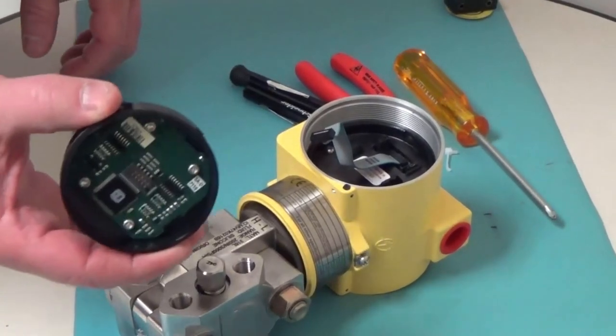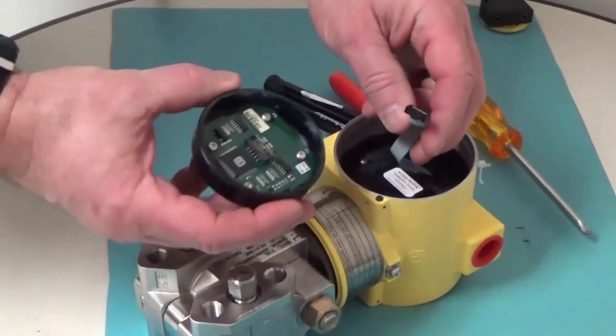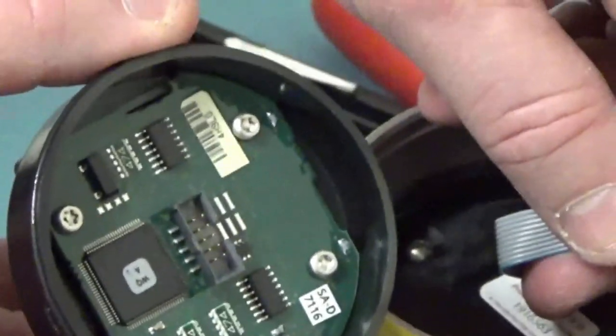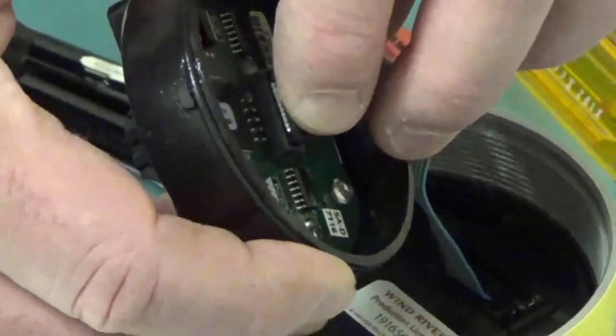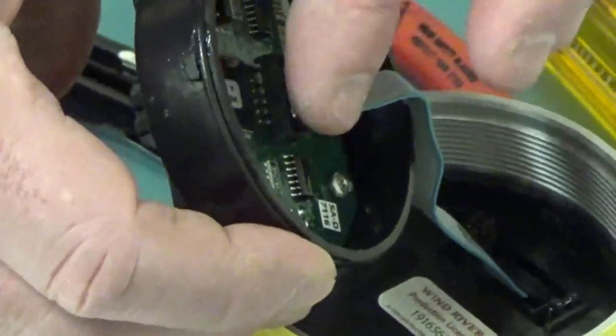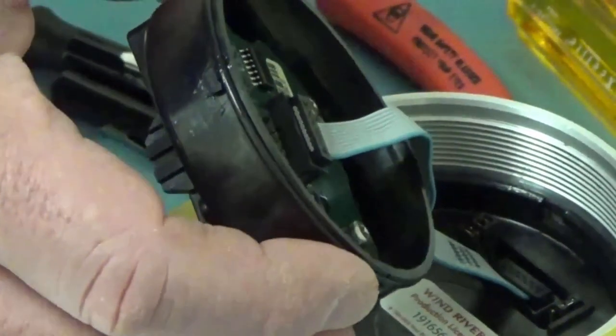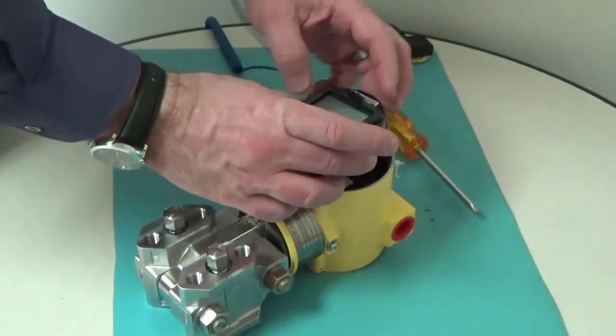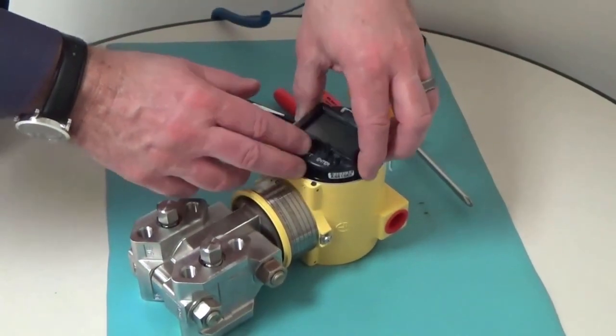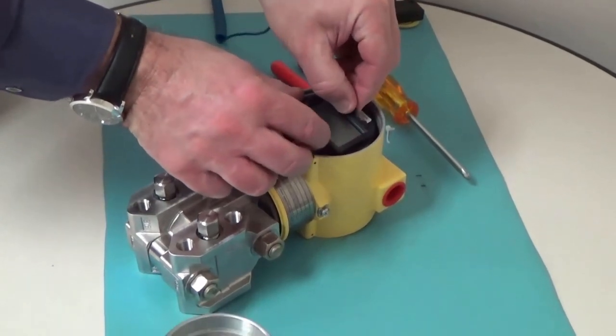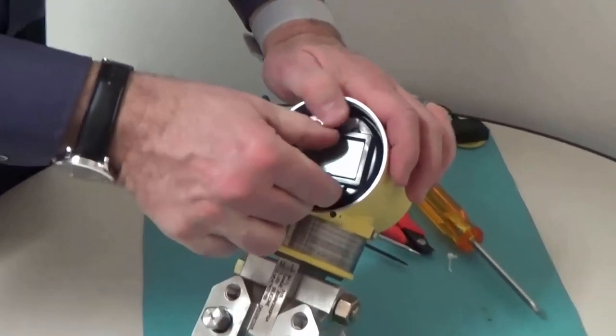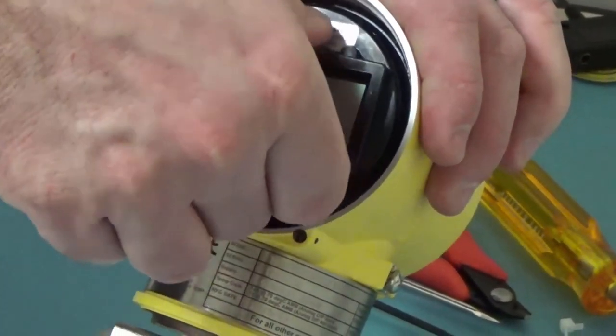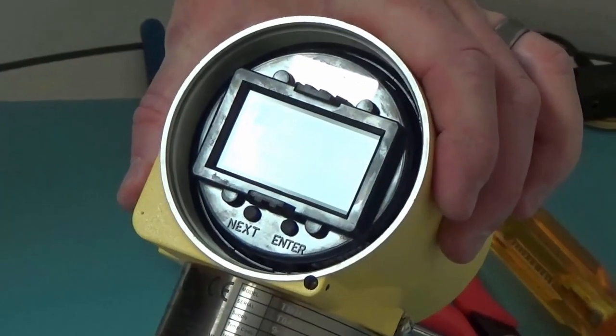We need to reconnect the display module. We can do that by plugging in the ribbon cable. It is keyed so it's obvious which way it goes into the connector on the back of the display board. You can feel when it mates properly with the connector. Then we just carefully bring that over and reinsert the display. It's just the opposite procedure to when we removed it. You can feel it when it clicks into place and then you turn it slightly to lock it. And everything is good.